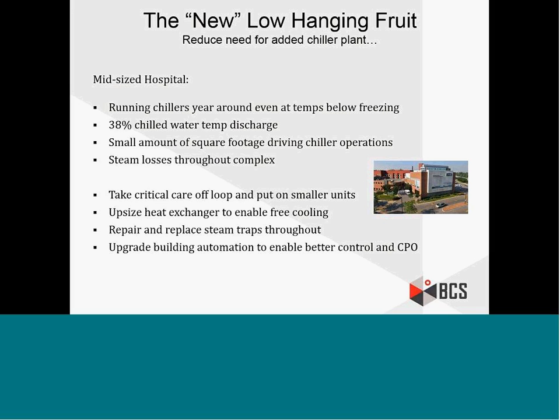Other measures include repairing and replacing steam traps throughout the complex, which will benefit the boiler side—they didn't have capacity issues, but they were really running those boilers hard, so that's going to mean quite a bit of savings. They're also going to upgrade their building automation, and between automation giving control of the spaces and adding the heat exchanger, we'll be able to introduce a chiller plant optimization program that extends the life of those chillers.